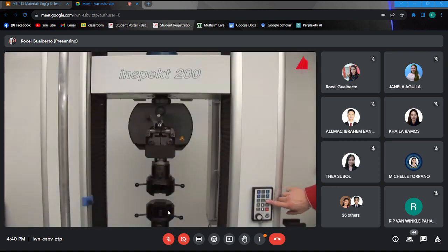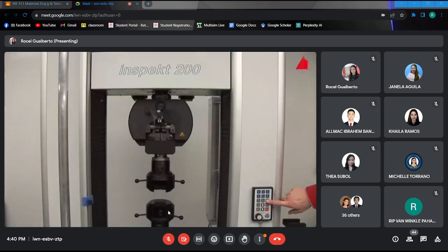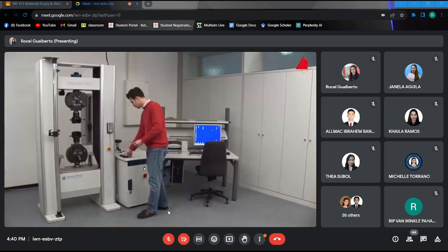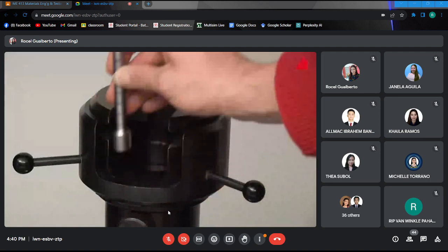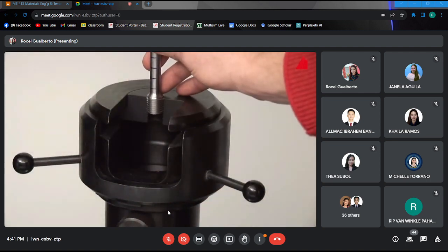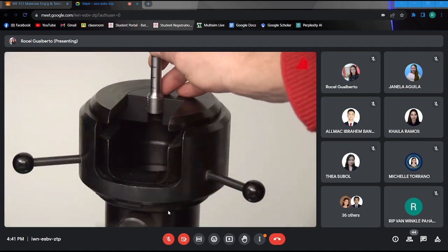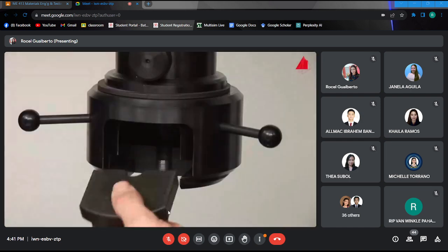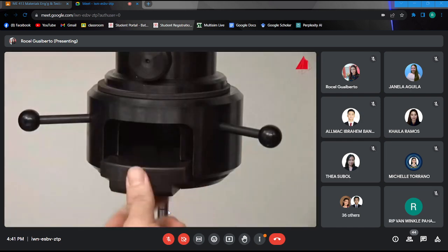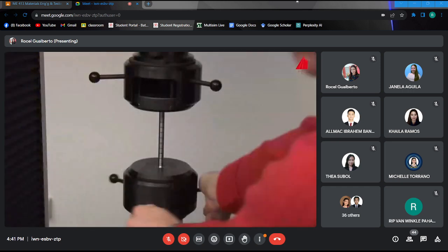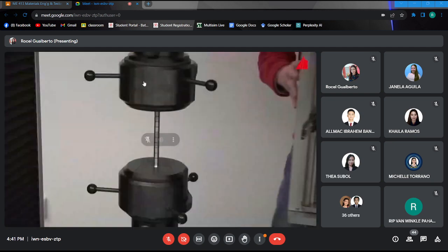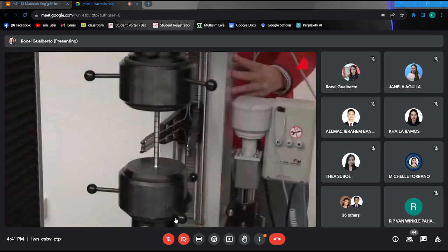Using a hand control, the tester moves the upper crosshead into its correct starting position. Now he can place the threaded ends of the test piece in the lower and upper grips of the testing machine. In the next step, he swings the extensometer into its working position and checks that everything is correctly prepared.